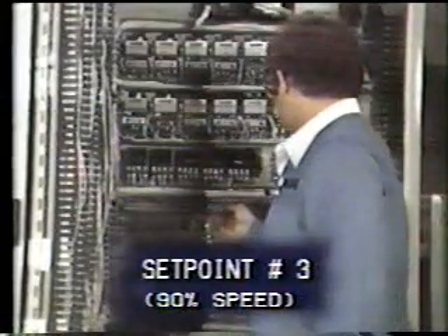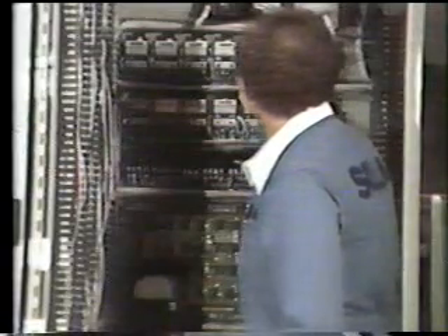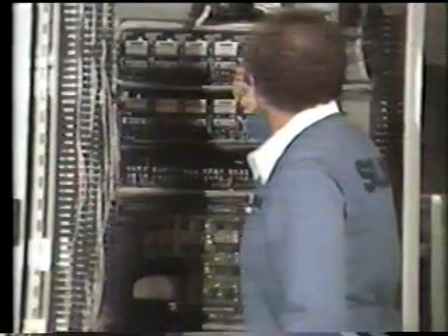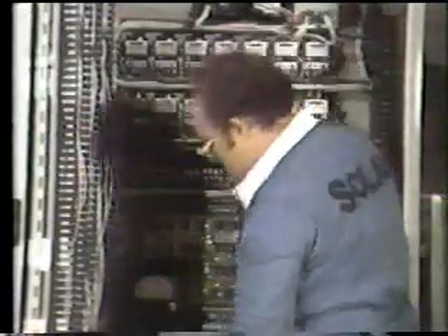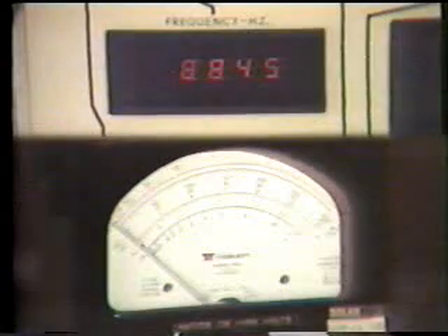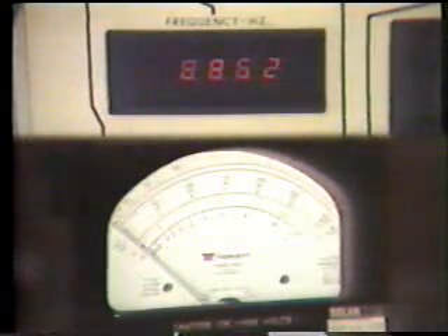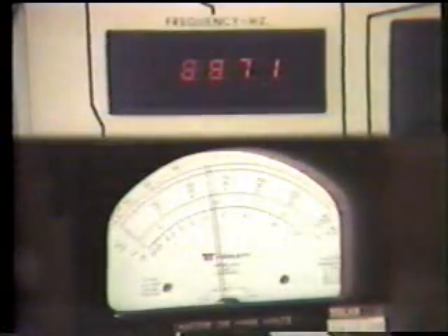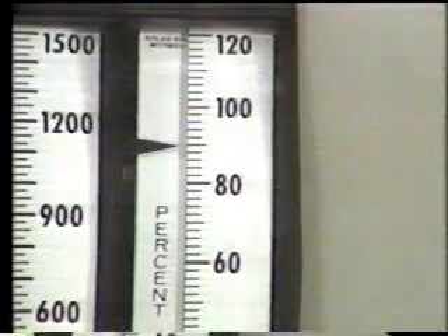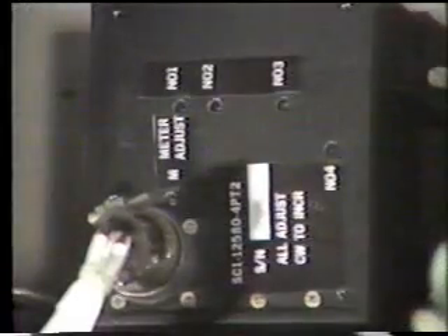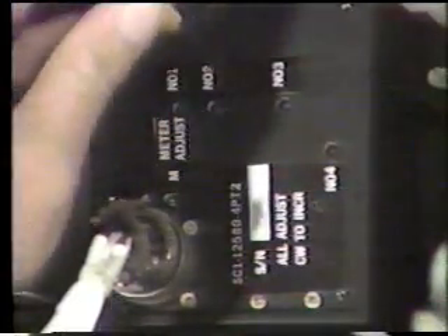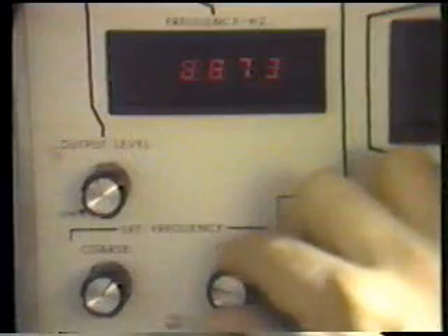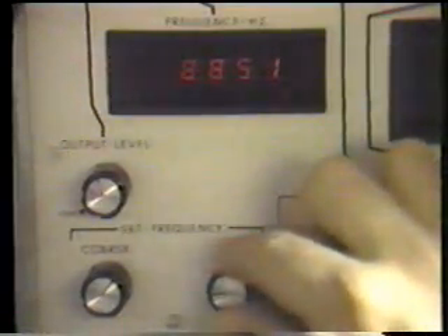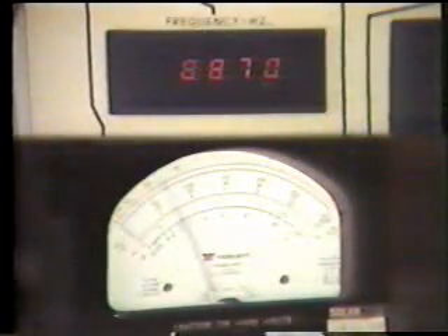Next, verify set point number 3 using the same procedures as before. Move VOM test leads to the wires attached to the switch contacts for 90% speed. Adjust the frequency output of the signal generator to transfer the contacts at 90% speed. Approach the set point slowly and observe the voltmeter for the switch transfer. Check the speed meter. It should read 90% speed. If the switch does not transfer at 90% speed, plus or minus 30 Hertz, adjust pot number 3. Decrease and slowly increase the signal generator frequency until the correct set point is reached. Observe the voltmeter for the switch transfer indication.